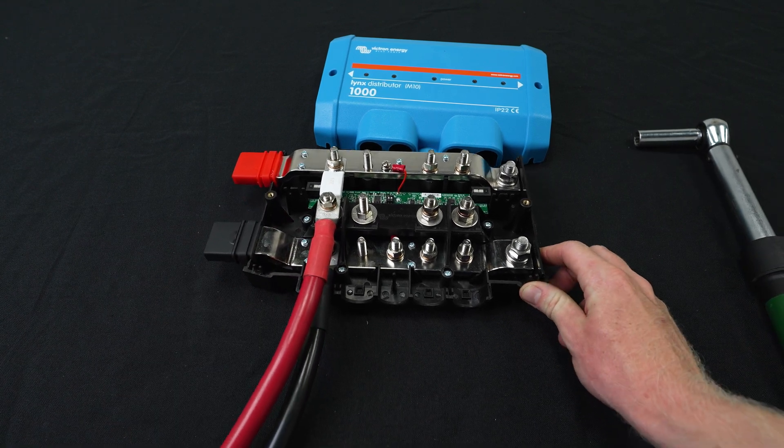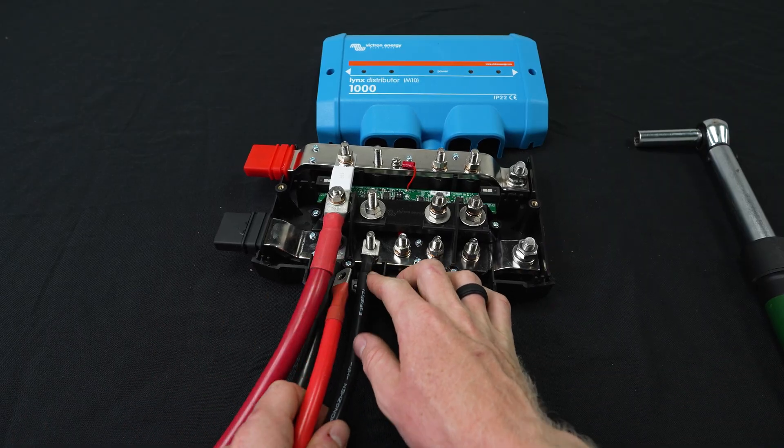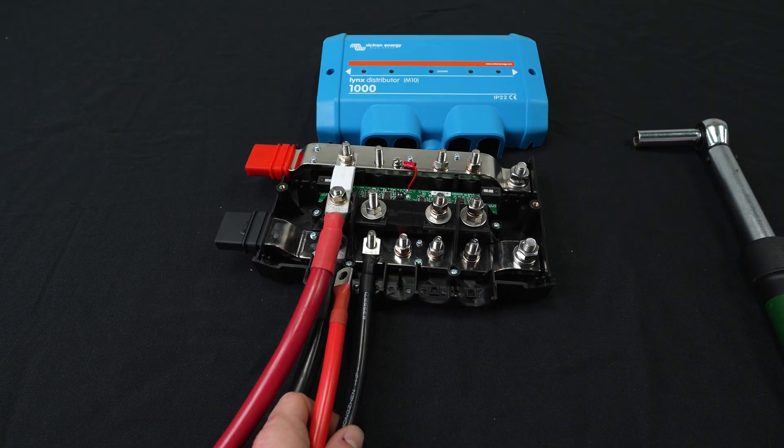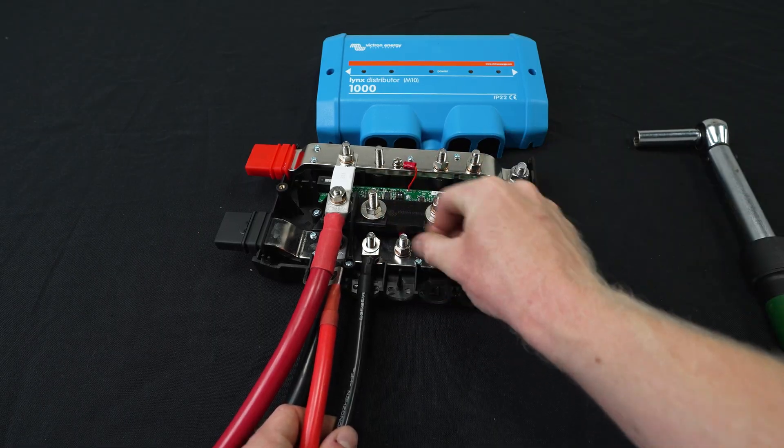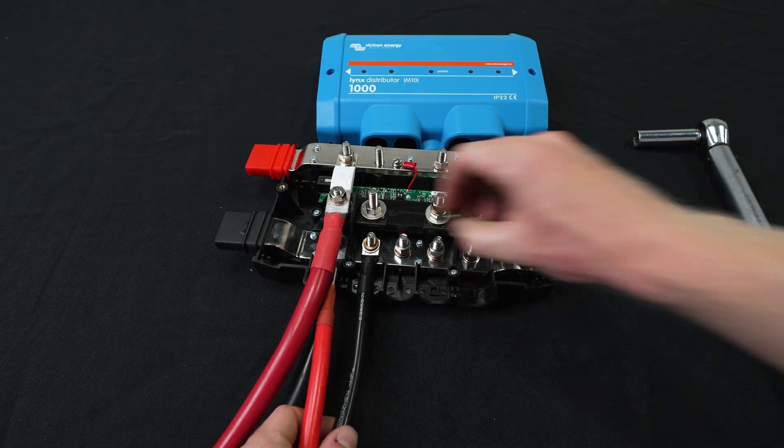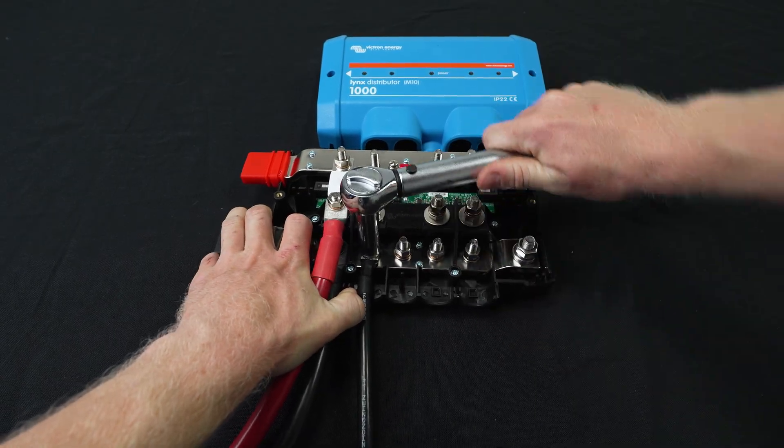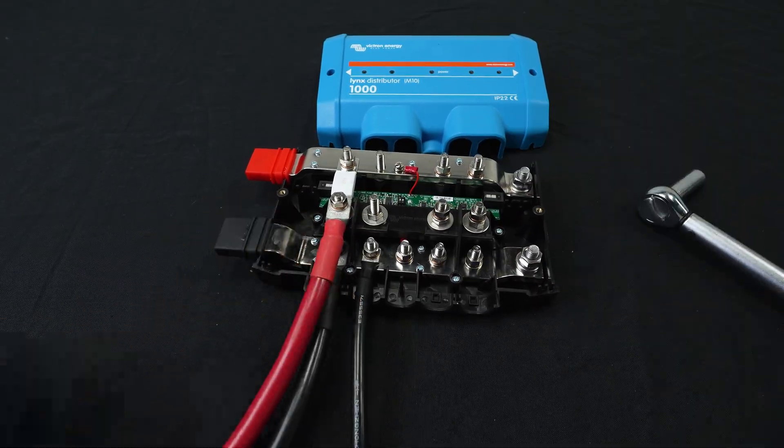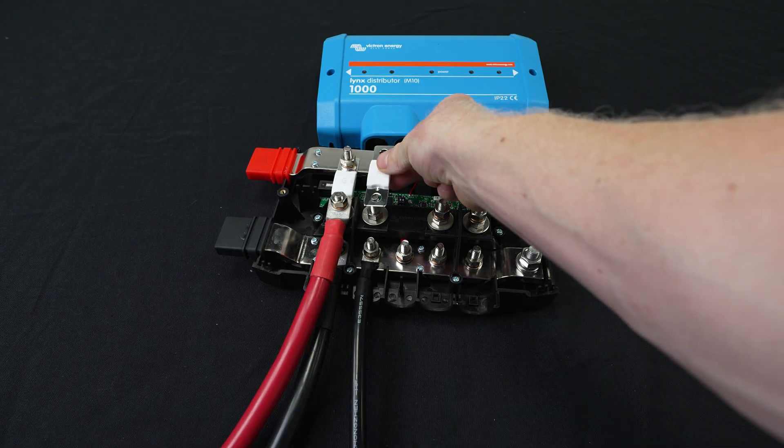All right, first one done. So we're going to do one more just for example. Next we're going to use a 2 gauge wire. Again 5/16 lugs, flat washer, lock washer, and our nut. For our 2 gauge wire, I'm using a 150 amp fuse.